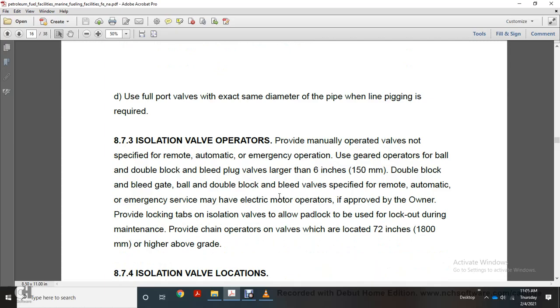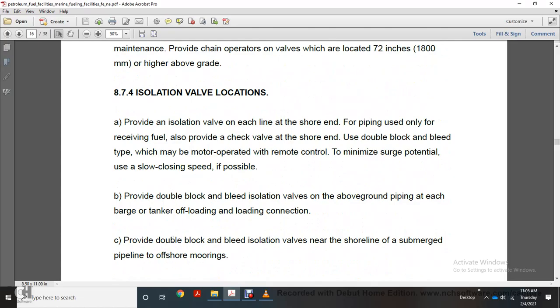Isolation valve operator: provide a manually operated valve if it is not specified with a remote automatic emergency operation. Use a gear operator with ball, double block and bleed plug valves larger than 6 inches. Double block and bleed gate, ball, and double block and bleed valves specified with a remote automatic emergency service may have electric motor operators, if approved by the owner, provide a locking tab on the isolation valve that allows a padlock to be used to lock out during maintenance. Provide chain operators on valves which are located more than 72 inches above the ground grade.